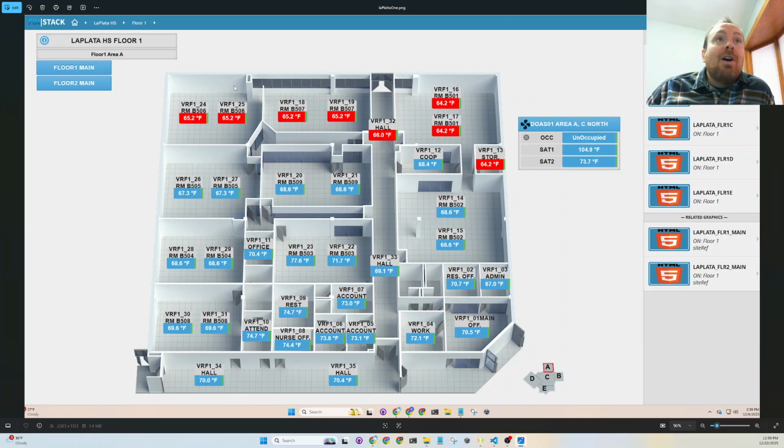but all these zones are drastically affected when the HVAC is off overnight, drifting down a good 7 degrees, like those ranges we've been talking about. Some of these interior zones are not affected. A couple of these interior zones even warm up, where it could be computer equipment or something, even when the HVAC is off.